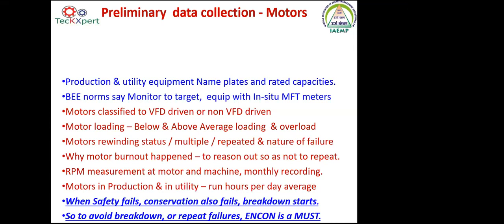And classify your motors, whether they are IE1, IE2 or IE3. If it is IE1, you have to change it out to IE2, and if it is going to be VFD driven, it is better to go for an IE3 motor. Definitely, with the percentage increase in speed, the IE3, which is an inverter compatible motor, is going to stand up better over its lifetime of, say, 15 years.